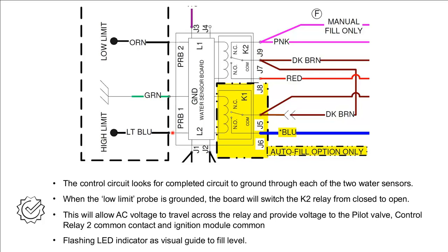The high limit sensor is mainly used for our autofill units. When water makes contact, it starts a 30-second countdown. When that countdown expires, the water will stop entering the unit.